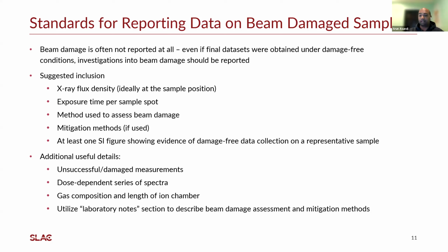Yeah, it's absolutely possible that over the course of many scans on a single sample spot, damage could be accumulating. So that's why we recommend comparing these many spectra collected on a single sample spot to see if there are changes from the initial spectrum. And also we have a recommendation to move to a new sample spot every so often and collect a low resolution scan, for example. That way you can confirm that the sample spot that you're measuring and collecting many spectra on is representative of what the rest of the sample looks like, and it's not affected by the exposure time.